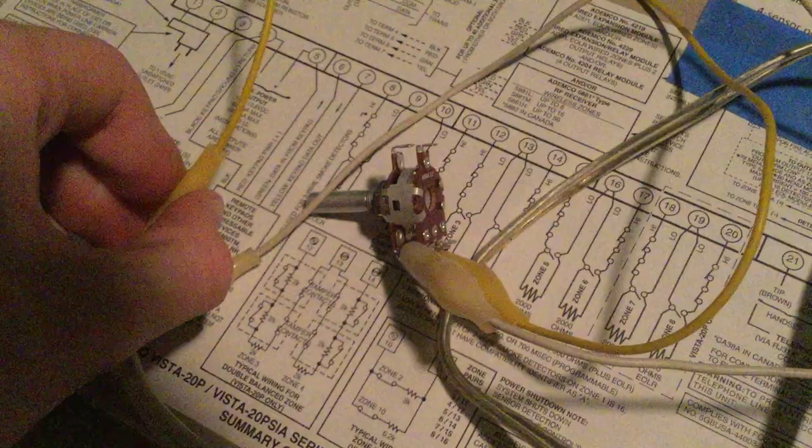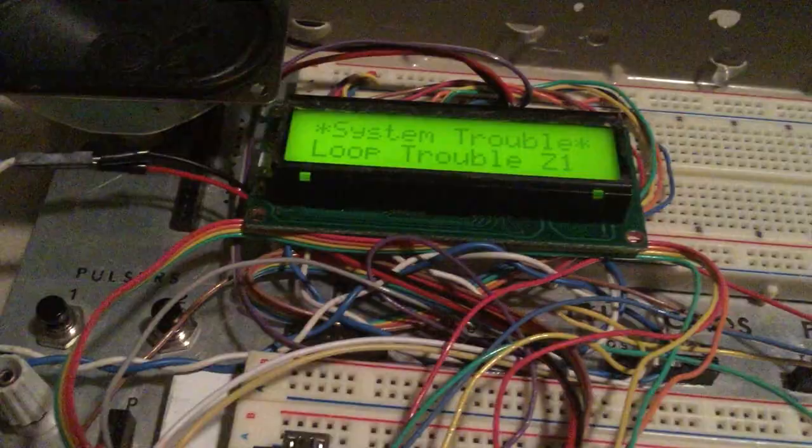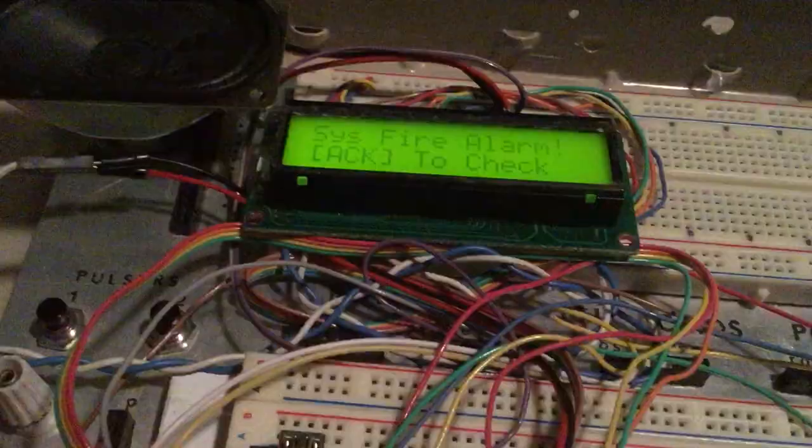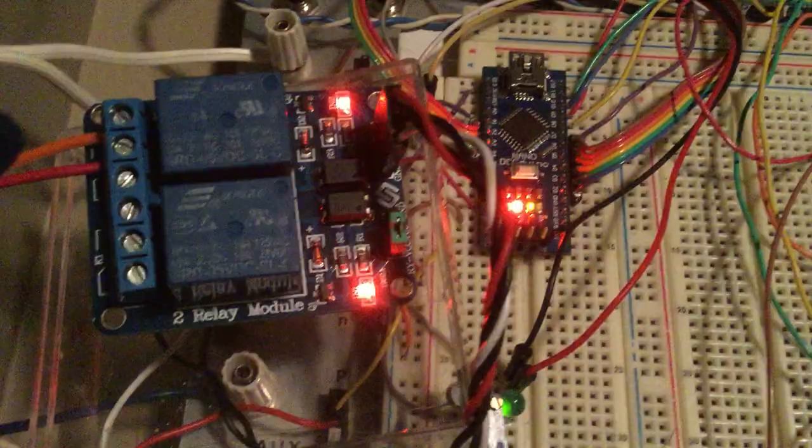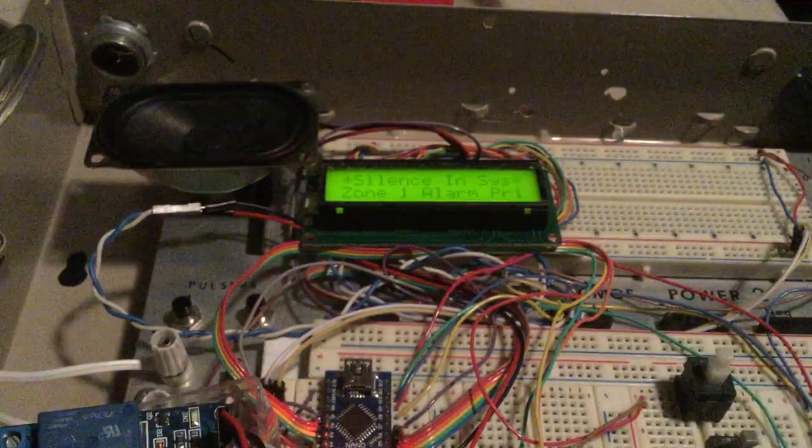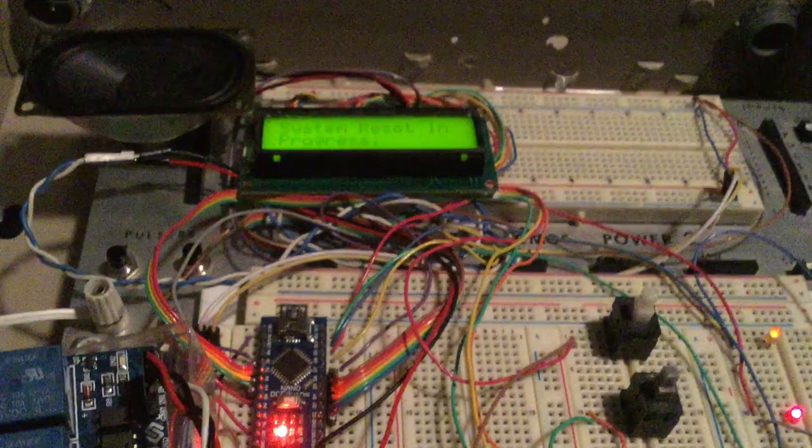There's a little few extra lines of code, so if I do activate the zone, we will go into alarm. And there's the Gentex SHG flashing. That is a very bright strobe, by the way. It doesn't look bright on camera, but that is blinding. So relay clicks off, silence in system. And zone 1 alarm primary. Let's reset now. All right.